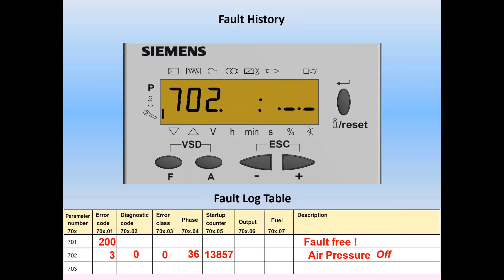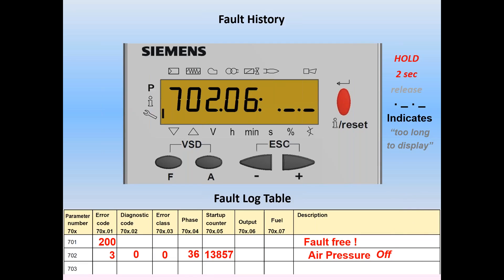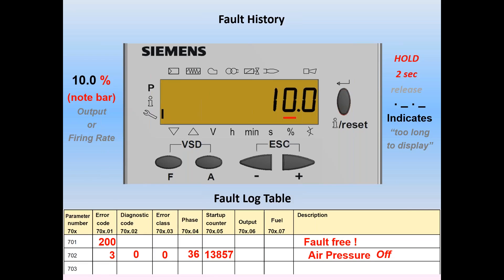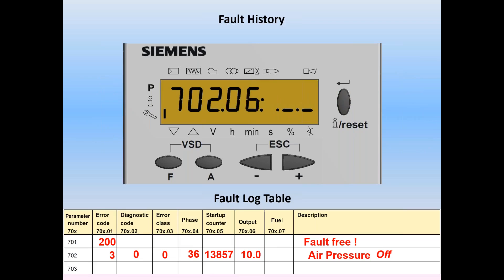Hit plus to move to index 06, which also shows dot-dash-dot-dash — the value is too big to display. Hold enter for two seconds and release. The screen shows 10, and it's 10% — the percent bar is lit up on the bottom. That tells us what units this is displayed in. We enter 10% firing rate into the bottom of the chart. Hit enter again and it returns us to index 06.